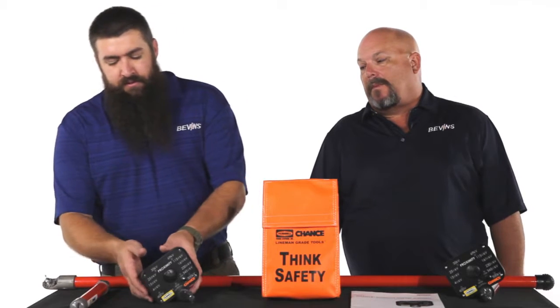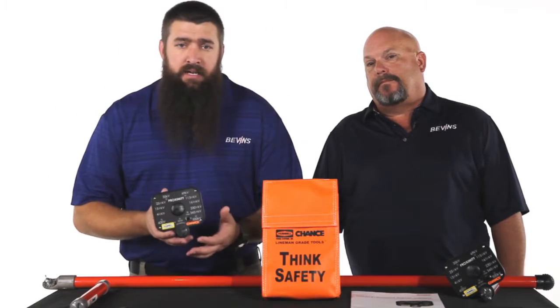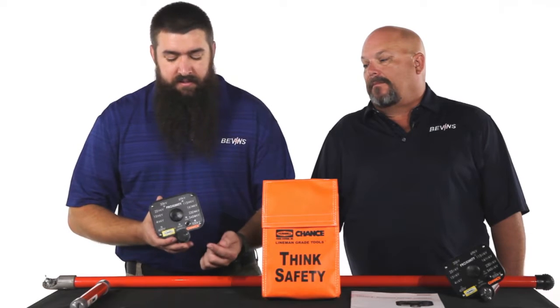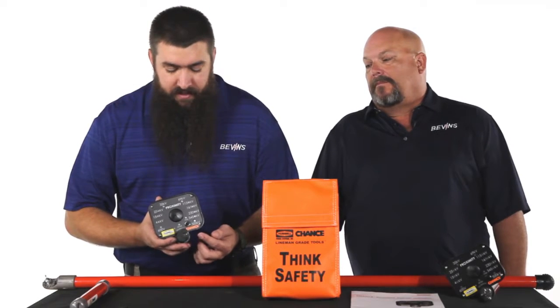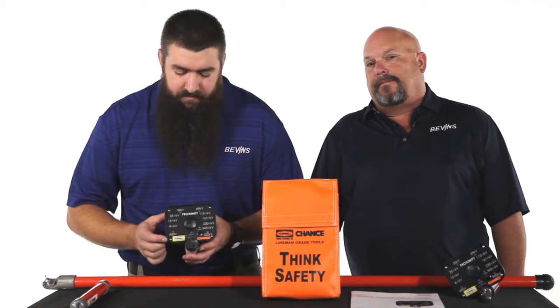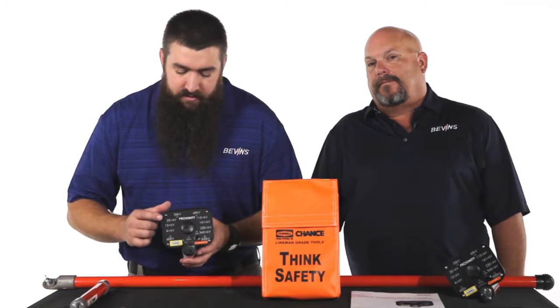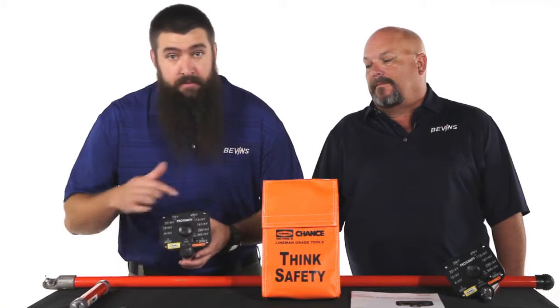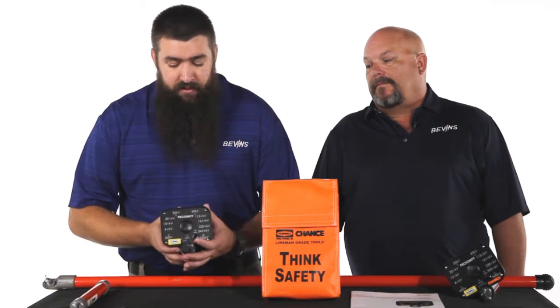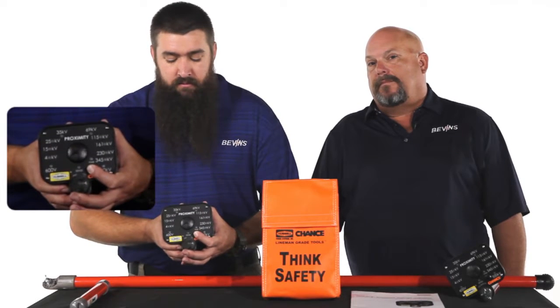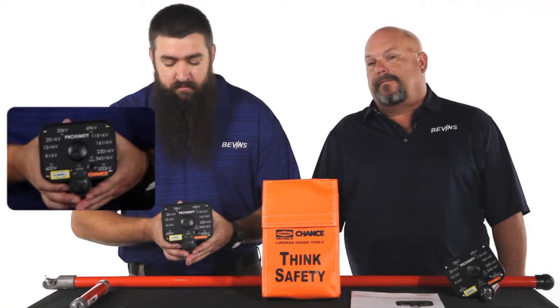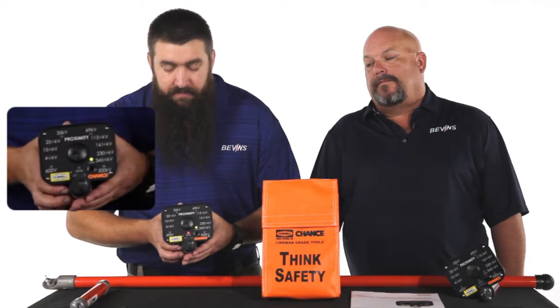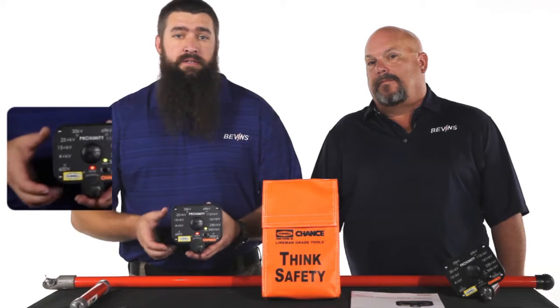Let's take them through the sequence to power up. So to turn this unit on, we have designed in a single button interface in the front that's easy to use even if wearing rubber gloves. And basically what you want to do is just press and hold the power switch until the audible beep is heard. At that point, the unit's going to go into self-test mode, and it's going to test each of the ranges and each of the LEDs from the bottom to the top in ascending order. So I'll just do that for you right quick. Press and hold. There's the beep, so let out. And the self-test is completed, and we've seen that each of the LED ranges is functioning.